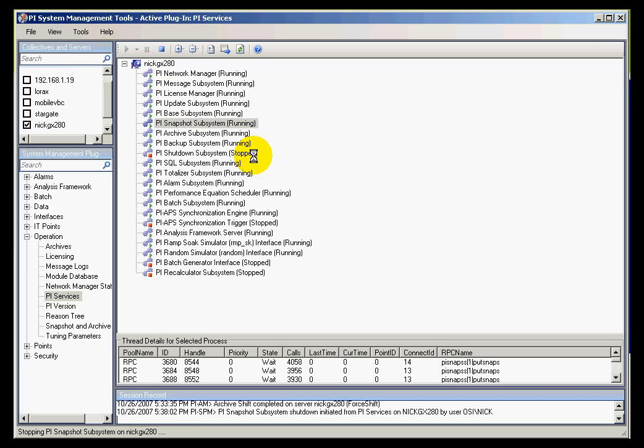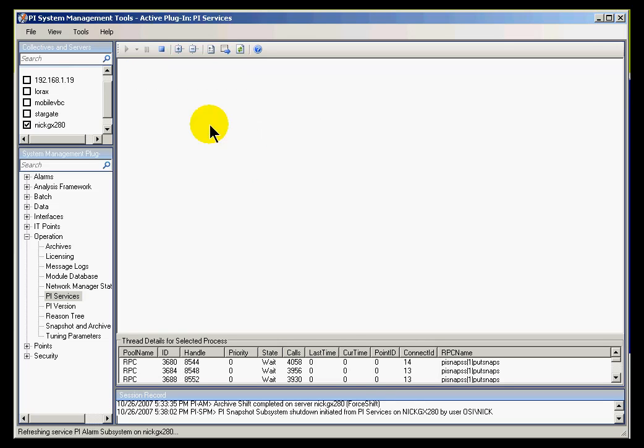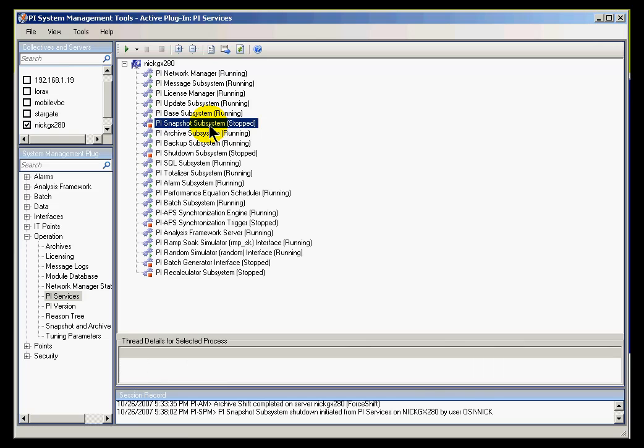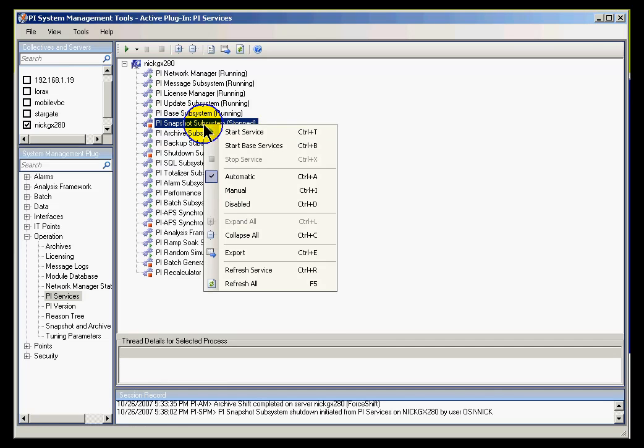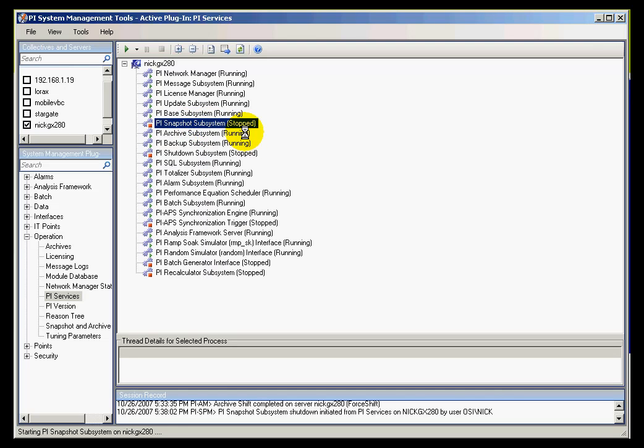So it's something that we use to demonstrate the utility of system management tools. But it's not something that does not have consequences if you stop and restart a service while the PI Server is running. So this may be something you simply wait for the next time that you shut down PI for maintenance or upgrade and restart.